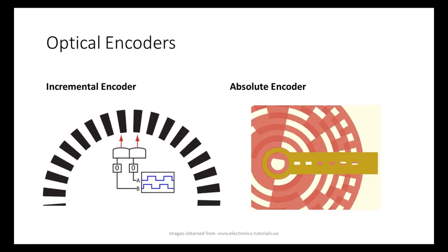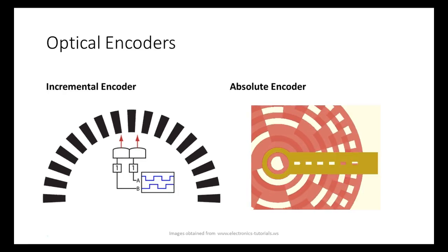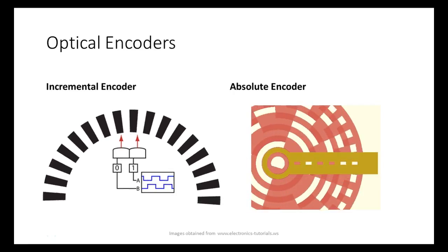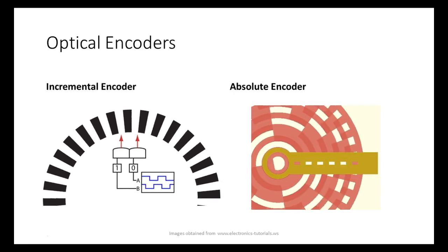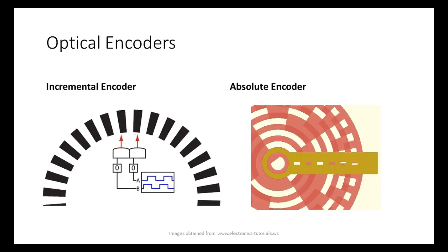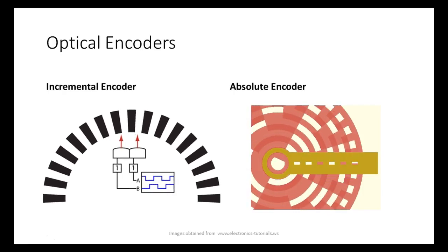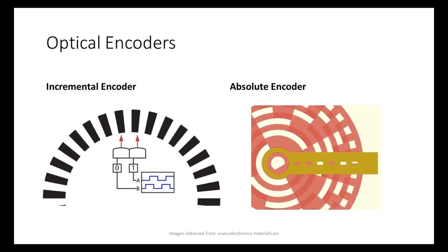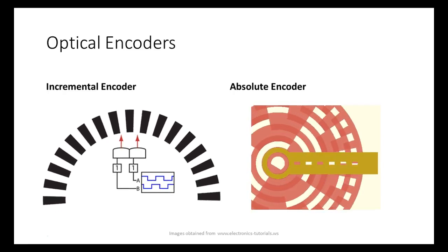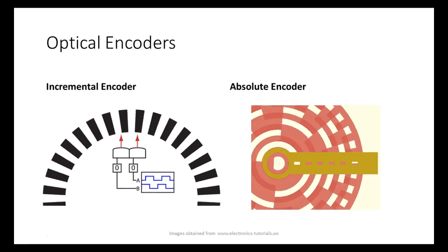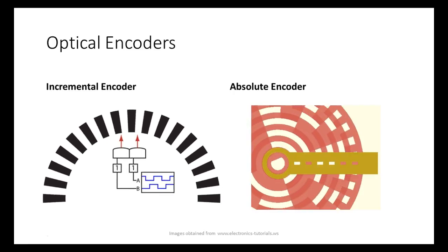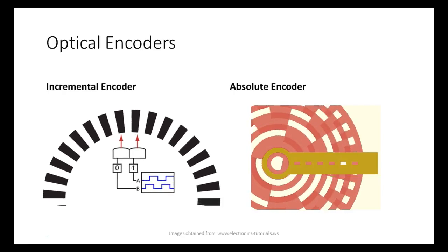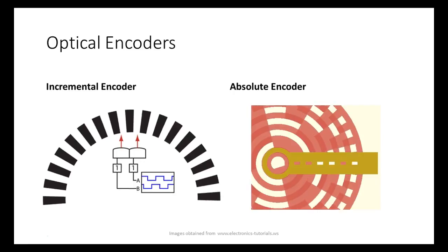So anytime you give directions, you're going to have to give it from a what? From an origin. So the robot has what we call an origin point. And the only problem is, if you lose power to those encoders, you lose the robot origin. And then when the program runs, it doesn't know where it's at, right? You understand? It's lost its origin. So most places that work with robots, part of their preventive maintenance is to go out there and change those batteries out at least once a year. Some of them do it more often.